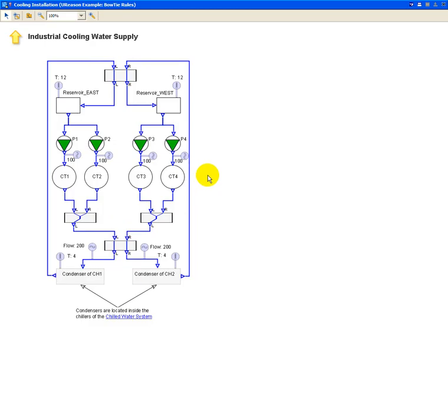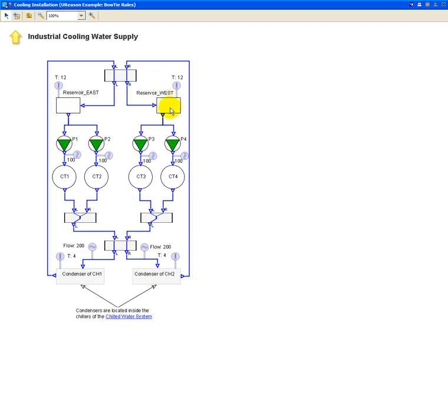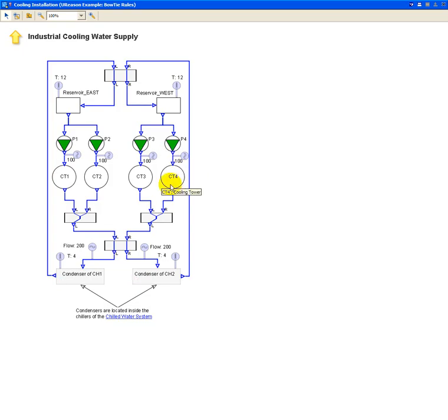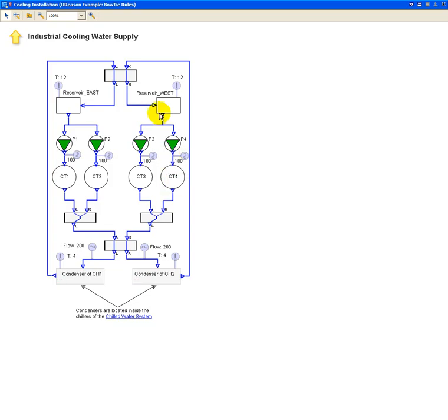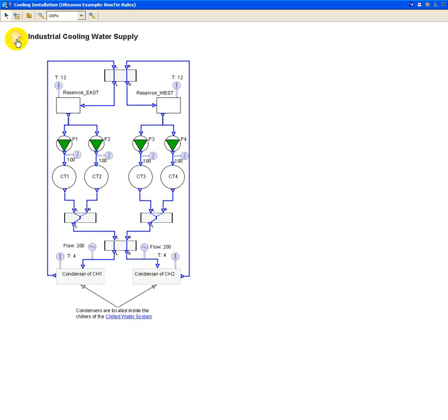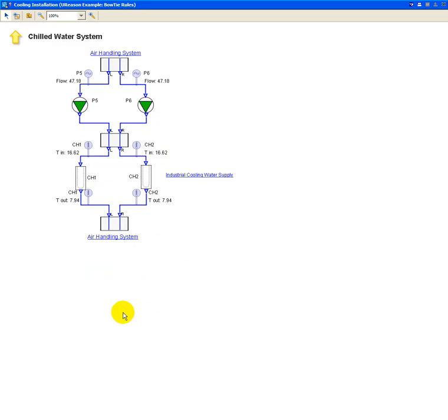And here we see the industrial cooling water supply unit that is also a kind of twin installation where we have two reservoirs, an east one and a west one. Each of them is actually feeding two pumps that are pushing water into cooling towers that are reducing the temperature of this water, and it's then pushed inside the condensers of both chillers. So that was a short description of the object model.